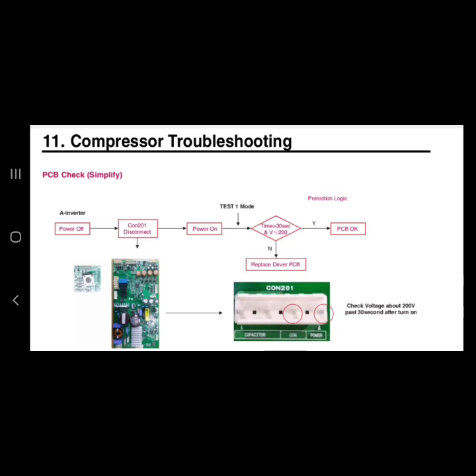Oftentimes no one takes the time out to check the board and to make sure that the board is supplying the proper voltage to the compressor. In today's tech talk I wanted to show you guys about this. What we're going to be going over is called the PCB check, which is basically checking the board to make sure that the board is actually giving the compressor the correct voltage. Due to the fact that these are linear compressors, they are 0 to 240 volts alternating current.